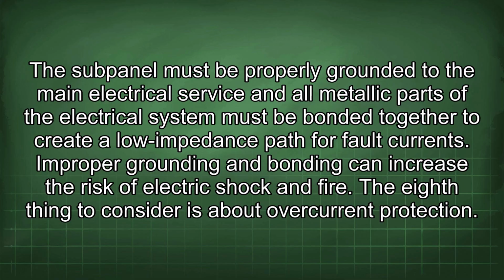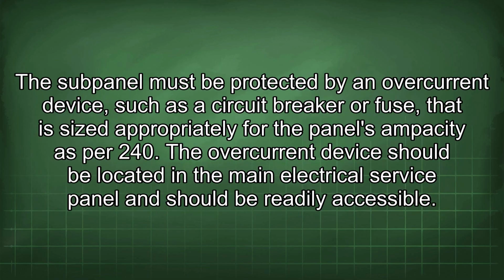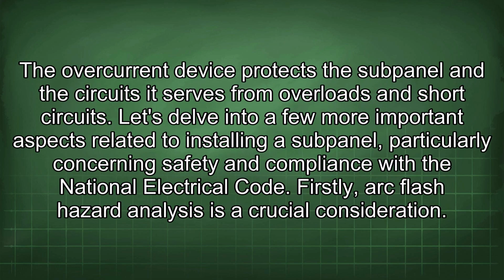The eighth thing to consider is about overcurrent protection. The subpanel must be protected by an overcurrent device, such as a circuit breaker or fuse, that is sized appropriately for the panel's ampacity as per 240. The overcurrent device should be located in the main electrical service panel and should be readily accessible. The overcurrent device protects the subpanel and the circuits it serves from overloads and short circuits.